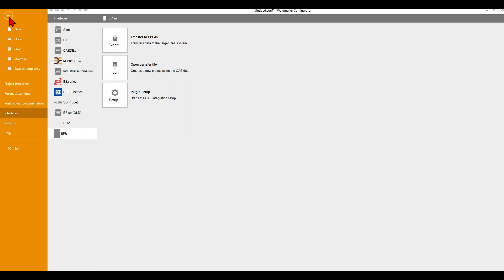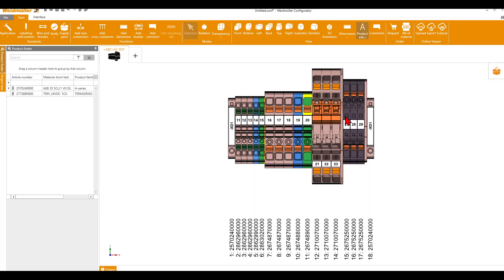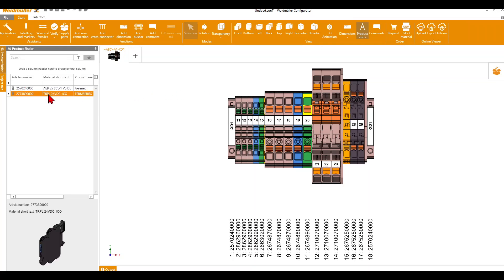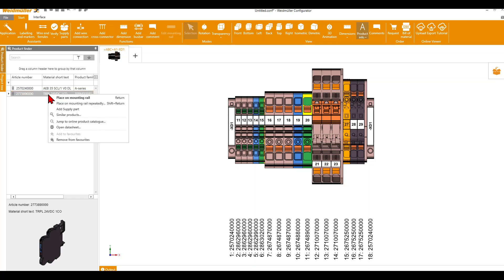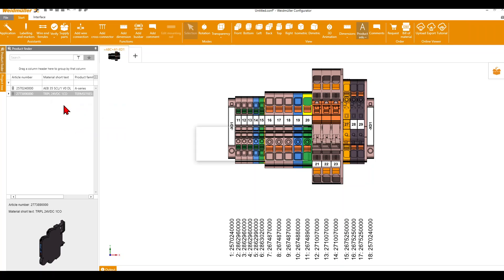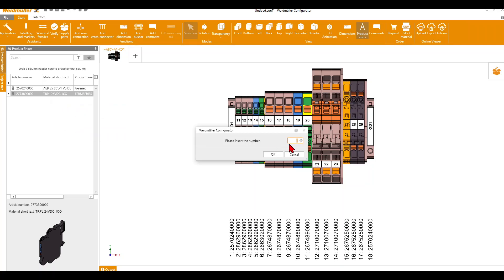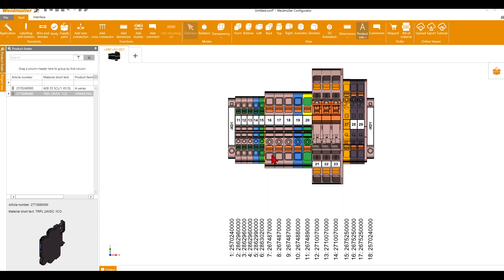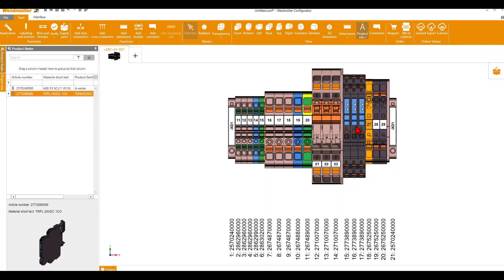Besides terminals, you can also add devices to your DIN rail. On this position, for example, we want to add relays. I have already marked these relays as my favorites, so they are easy to find. I make a right-click and can select Place on Mounting Rail Repeatedly — that means I can select the quantity. For example, I want three. Click OK, and I now get three relays on this position.